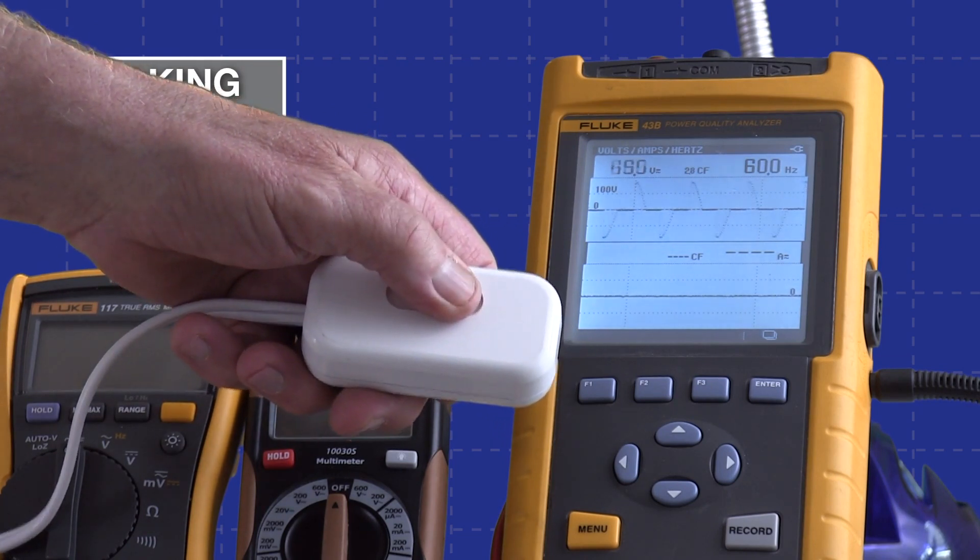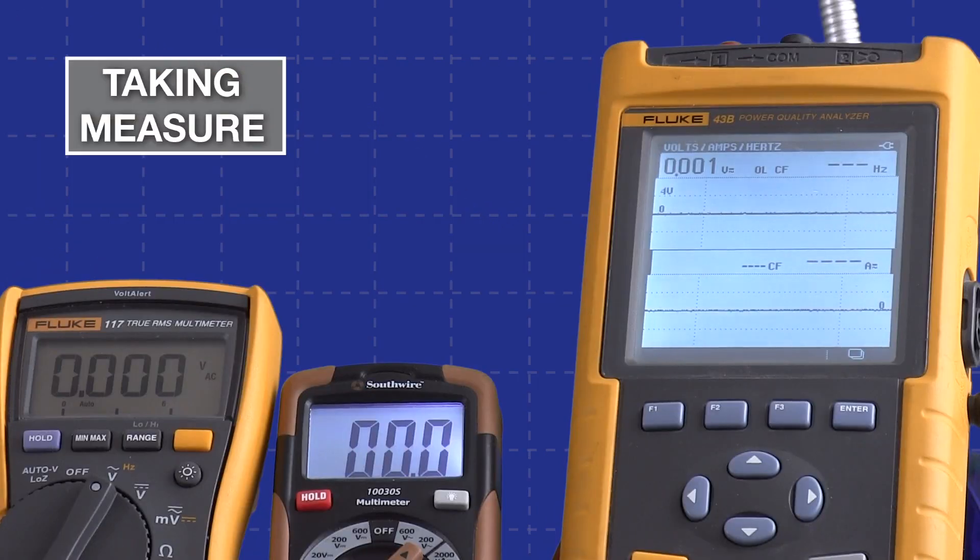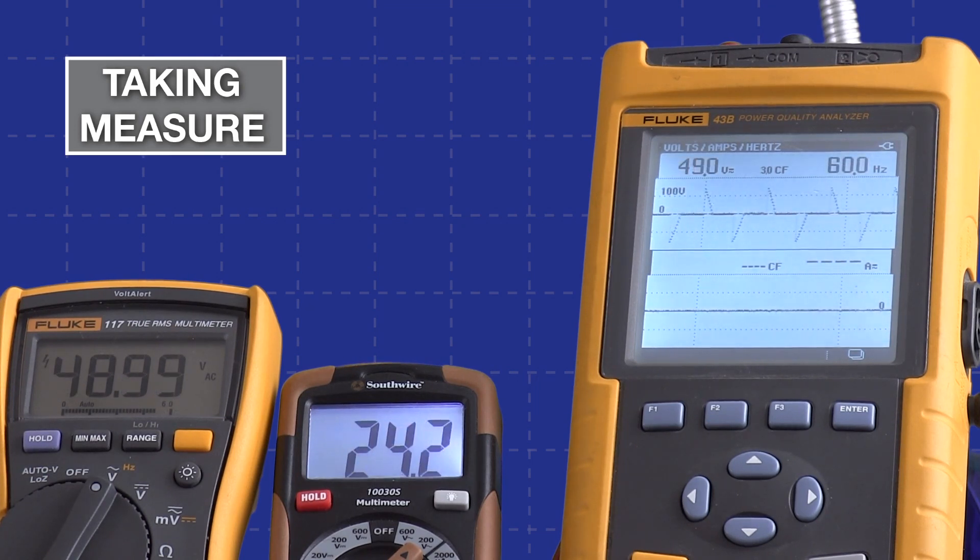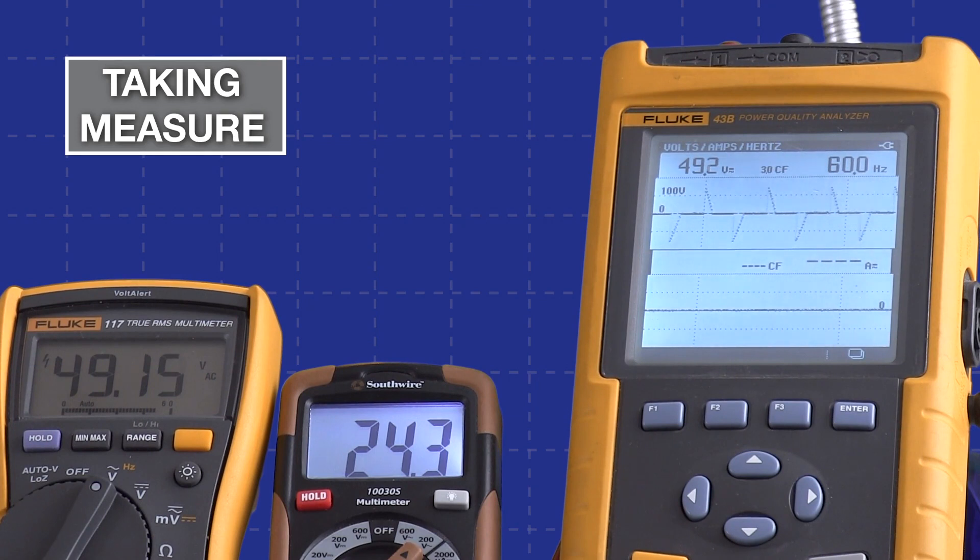We now have all three of our test instruments connected to our dimmer circuit, and I'm going to operate the dimmer and we'll see what happens to the voltage on each of these instruments. I'll start now and we'll go up a little bit. If you look, you should see 48 or 49 volts on the Fluke power quality meter with the shark fin, and then the Southwire showing 24, but the Fluke 117 is also showing 49. So the two Fluke meters show the same voltage.